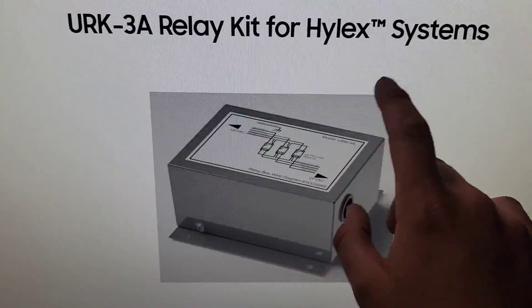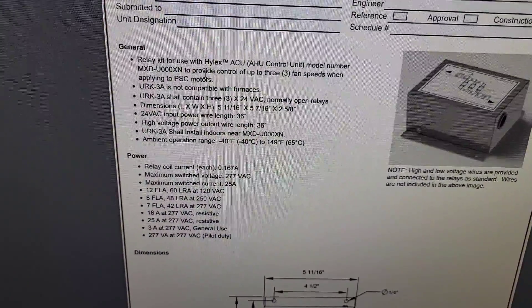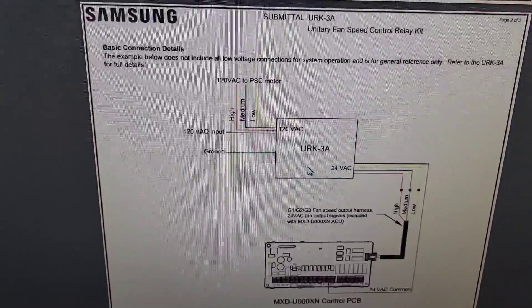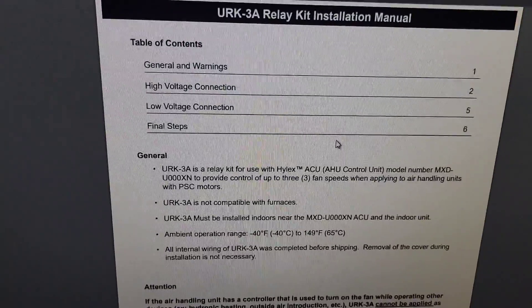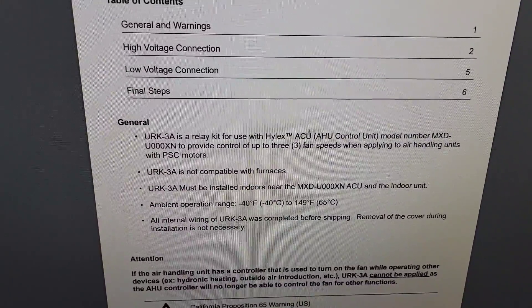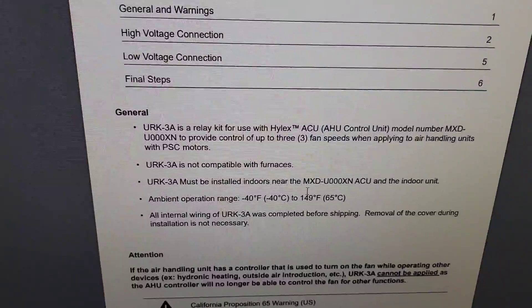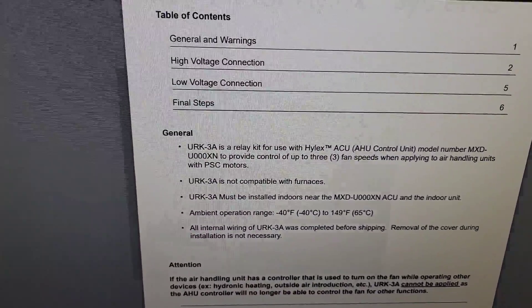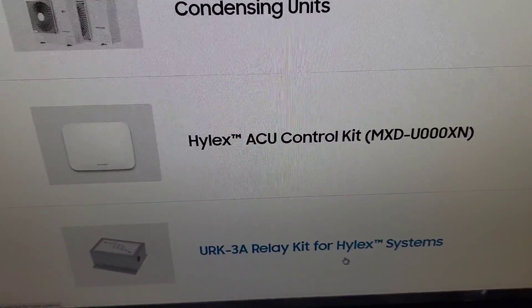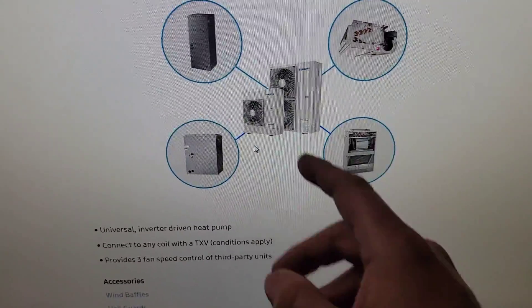More information you may need about installing the Hylex systems — this is a relay kit for those systems. The URK3A relay kit for the Hylex ACU model provides control of up to three fan speeds when applied to air handling units with PSC motors. But it says right here it's not compatible with furnaces and must be installed indoors. So you may need this relay kit. This is the ACU control kit — I didn't have to have the relay kit because I was installing these on furnaces. You can get this from two tons all the way up to five tons.